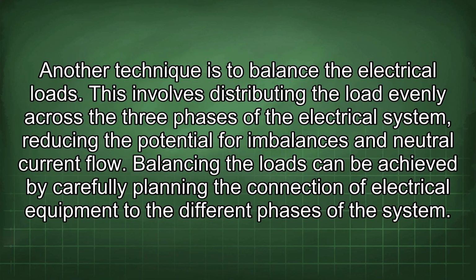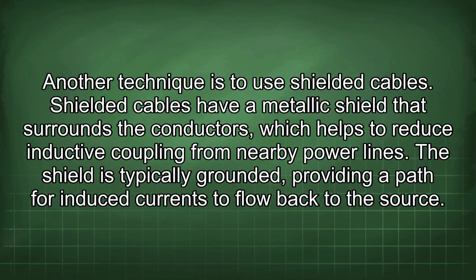Another technique is to balance the electrical loads. This involves distributing the load evenly across the three phases of the electrical system, reducing the potential for imbalances and neutral current flow. Balancing the loads can be achieved by carefully planning the connection of electrical equipment to the different phases of the system. Another technique is to use shielded cables. Shielded cables have a metallic shield that surrounds the conductors, which helps to reduce inductive coupling from nearby power lines. The shield is typically grounded, providing a path for induced currents to flow back to the source.